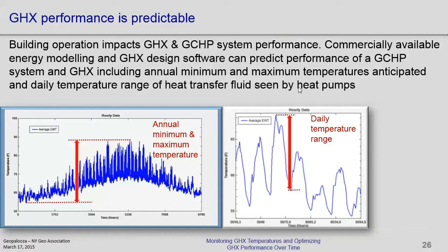The peak load, the loads on the building change on an hour-by-hour basis, depending on what's happening. You could have a cooling load at 7 o'clock in the morning, where there's a few people in there. You might have a cooling load of 5 or 10 tons. At 9 o'clock, a bunch of lights are on, computers are all on, a bunch more people are in there. You might be up to 30. At 3 in the afternoon, you've got a whole bunch of people working away, and more lights are on, and it's got the sun beating in on the west facing glass, and the lights are all on.